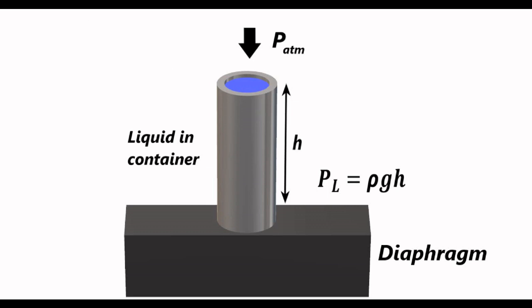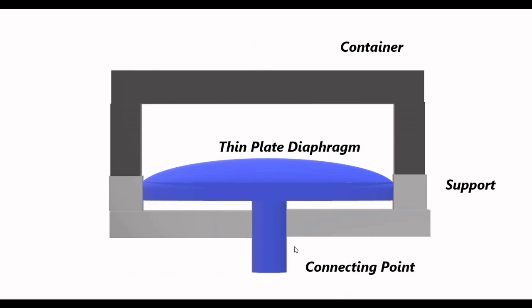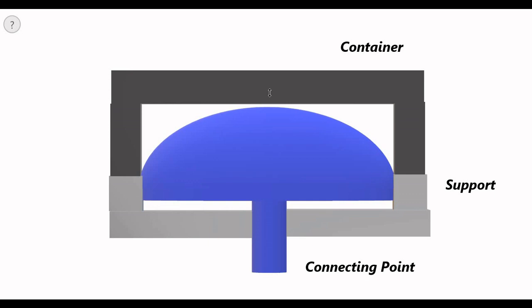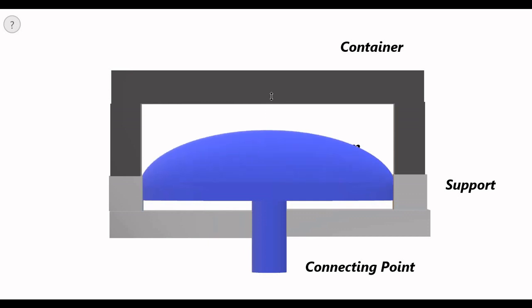Here let us try to understand this whole thing from a three-dimensional perspective. We have a liquid in a container, at a certain height h above the reference. The diaphragm is connected to the liquid column through the connecting point, and it measures both the liquid column pressure and the atmospheric pressure. The liquid column pressure changes because of the changing level or height of the liquid. This whole thing comes in the form of an encapsulated chamber container. When it is subjected to the pressure, the diaphragm either expands or compresses. This is the maximum point, where the tip of the diaphragm touches the container. Because of the liquid column pressure combined with the constant atmospheric pressure, the thin plate diaphragm undergoes expansion and compression. Expansion is the maximum point; compression is the minimum point at the bottom.